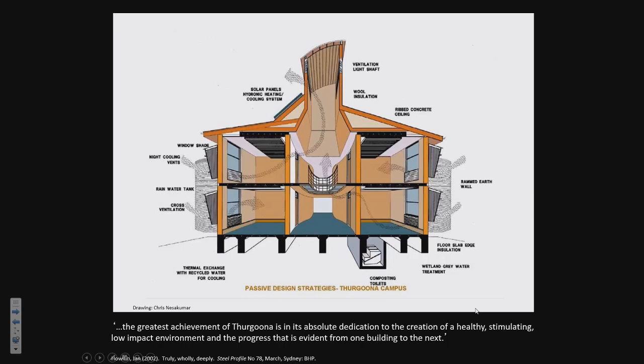In summer mode, when the temperature outside drops below the temperature inside, the low-level vents under the windows open up. There are louvers above the doors, and we rely on occupants to open those in hot weather. The air is then drawn through with thermal buoyancy and through the thermal chimney, bringing cool air through the building and out the chimney, usually at night.